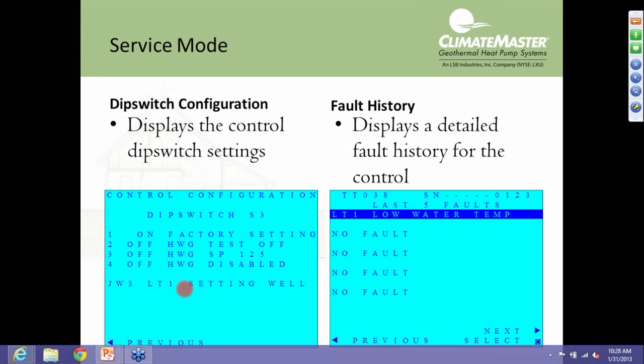Oops, apologize there. Dip switch bank 3. Again, there are 4 dip switches on that bank. Number 1 should always be in the on position. That is so our communicating thermostat will communicate with the DXM2 control board. It also shows you on this screen if the JW3 jumper was cut or not. If it's not cut, it'll say well. If it does get cut, it'll say loop.